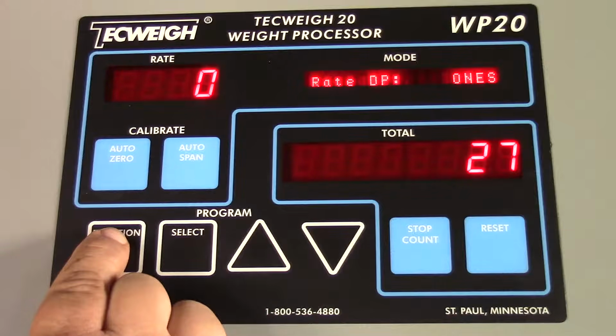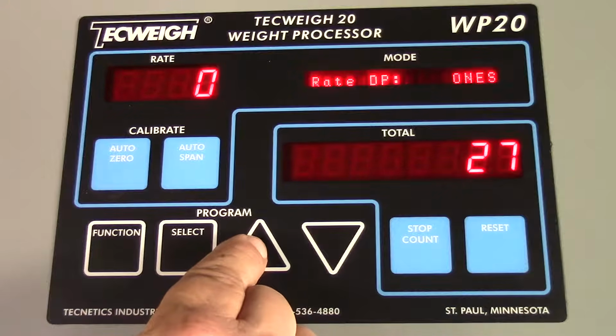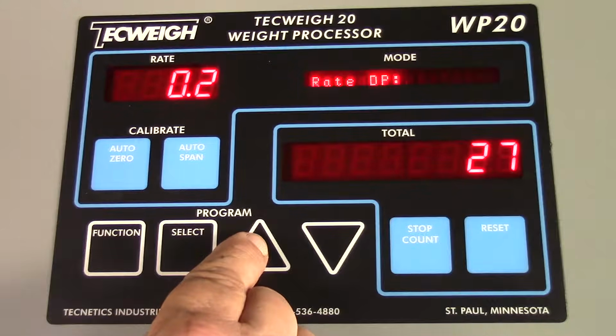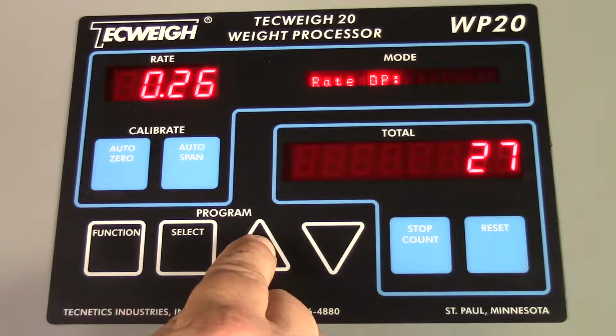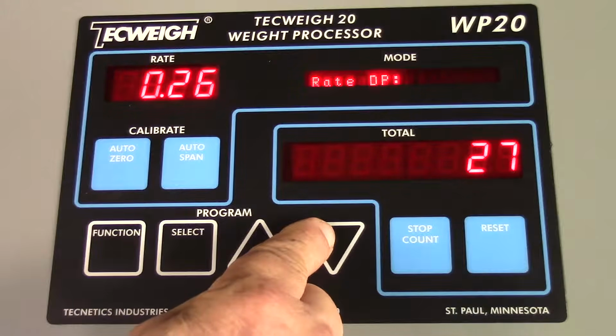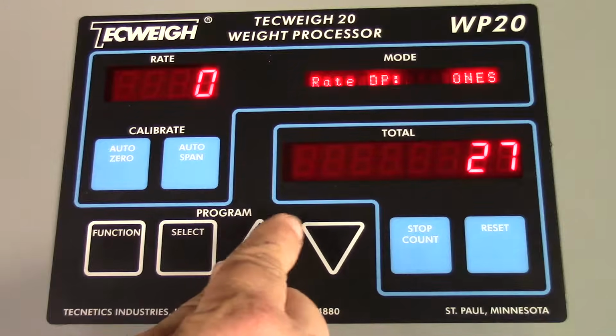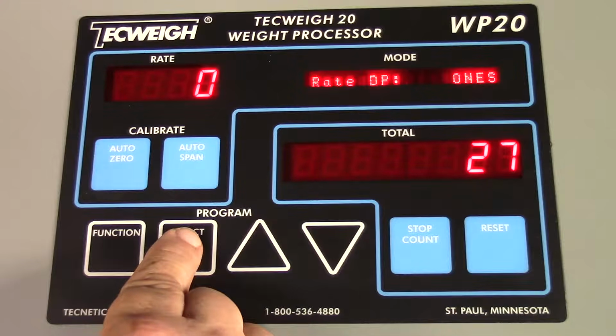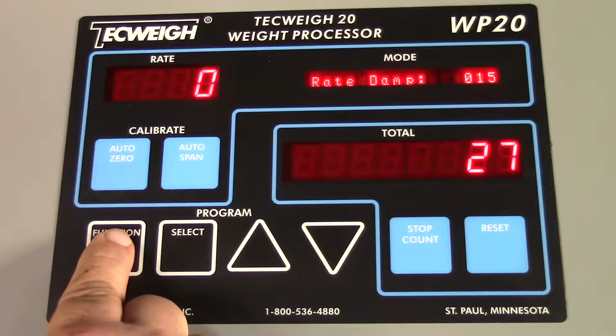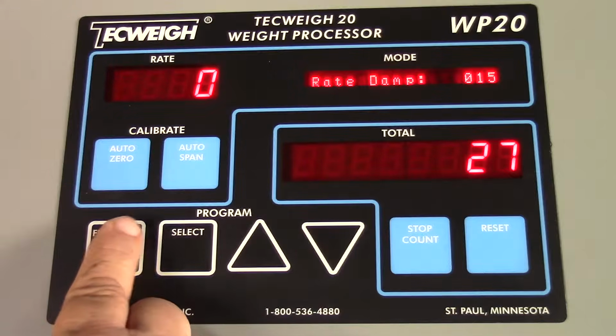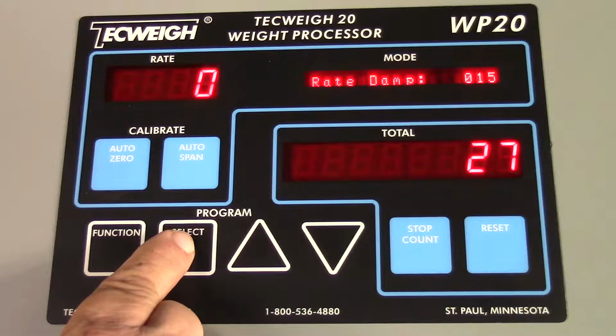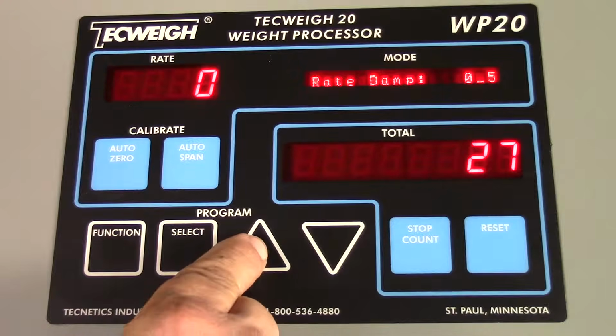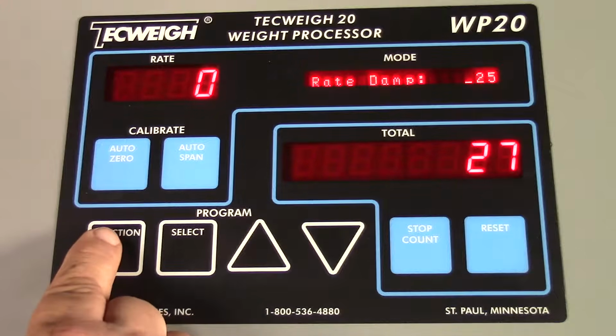Rate decimal places, generally we leave it at 1, but we could change that to something else, and you could see how it affects the rate display. We're going to change it back to 1s and keep moving forward. We'll acknowledge that parameter by hitting select, and we'll keep hitting function to go forward. This would be the rate damping. Sometimes I'll change that just to slow down the movement on the display, maybe up to like 25, for example, which I did in this example.